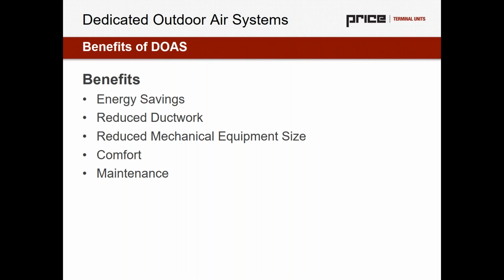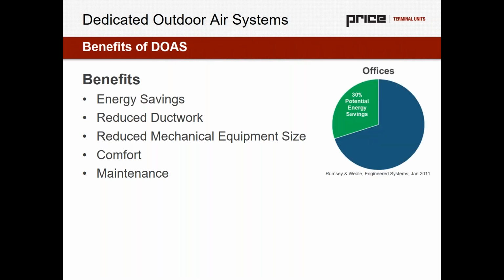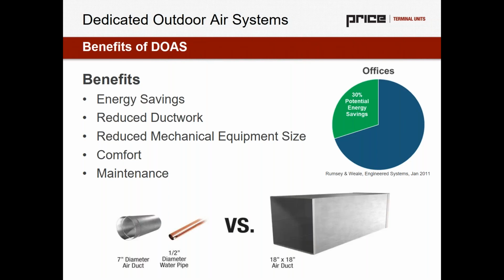And this results in some significant benefits. We have benefits in energy savings. We generally see about 30% potential energy savings when looking at open office environments with dedicated outdoor air systems. We're also seeing significantly reduced ductwork. That reduced ductwork comes into play because the volumetric heat capacity of water is so much greater than air. At standard conditions at sea level, the volumetric heat capacity of water is 3,500 times greater than that of air. So extremely significant.